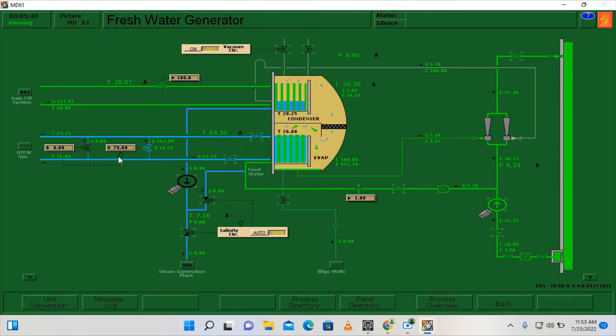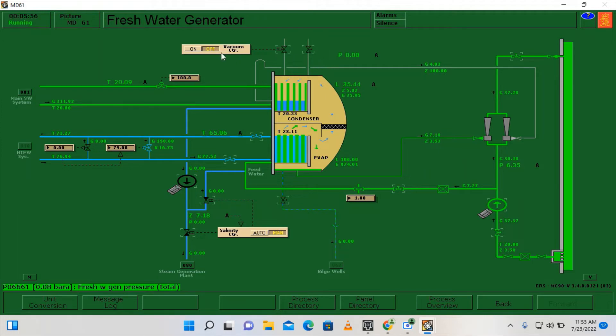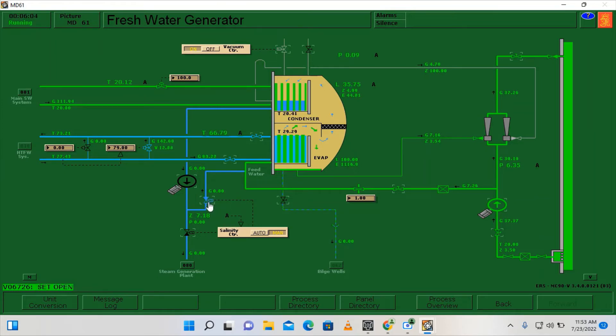It should maintain around 79 degrees Celsius and we need to make sure that the pressure here will not exceed too much. Afterwards I need to switch on the vacuum controller and manually open the dumping valve and start the distillate pump.